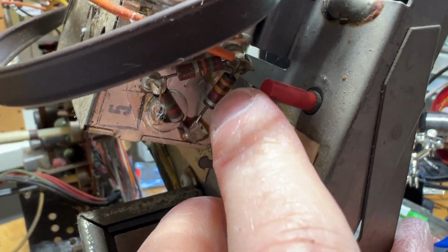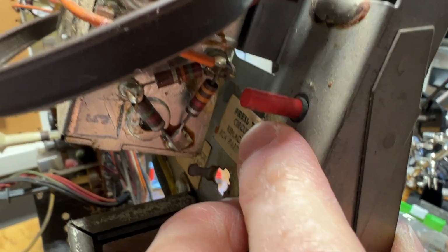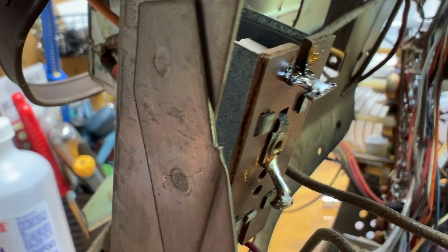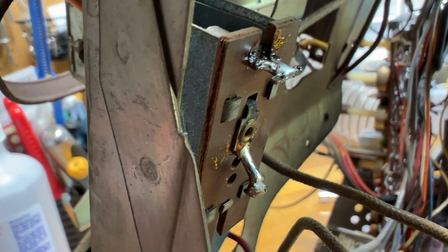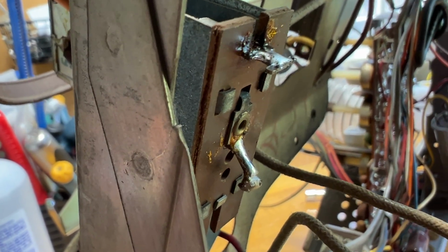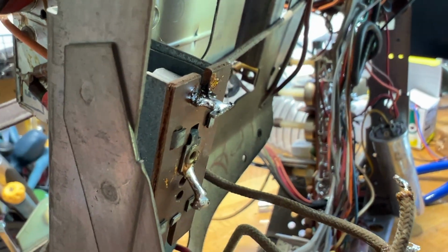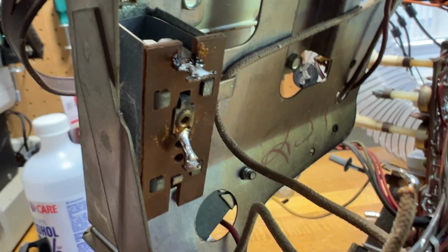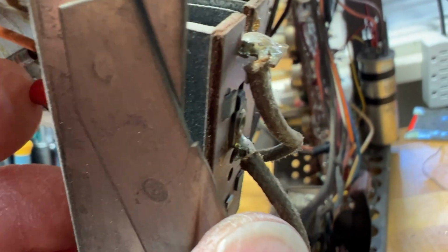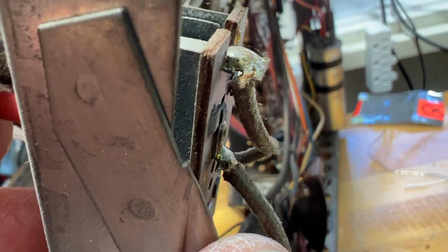This circuit breaker here is flaky. It sometimes makes contact, but most of the time it doesn't. The circuit breaker, which reads at best about 17 ohms and at worst infinite, cannot be trusted. I will probably end up replacing it with a fuse instead of another breaker. I might be able to acquire one of these breakers, but I doubt it. It would just be better to have a fuse here, probably slow acting. I'd have to check the circuit to see how many amps.